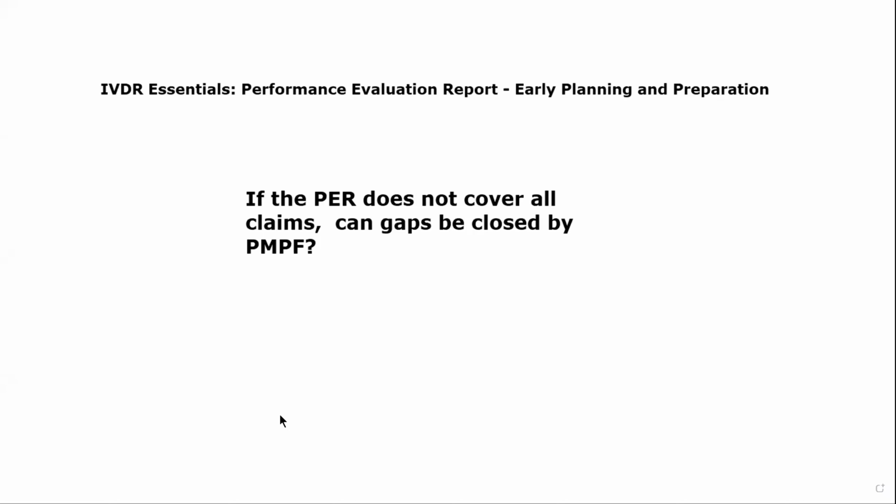So this can be a challenge. And this kind of comes down to the difference between a claim and a purpose. The claims are put out by marketing. And so while your device may be used for a particular indication, or there's no reason why it couldn't do a particular indication, if you do not have data supporting that indication, that can be very problematic when you're doing your PER. You may need to go in and maybe you can establish equivalence with a prior test and be able to use data from a similar device, if you can claim equivalence with another device that's on the market.